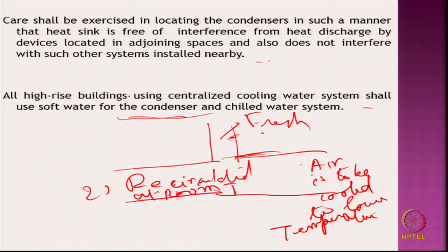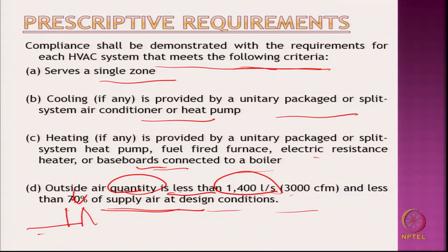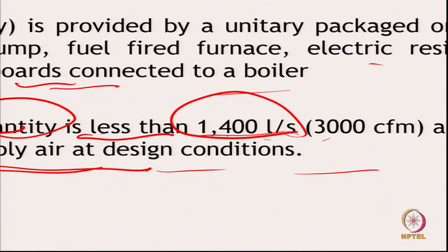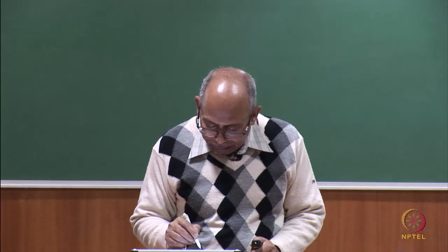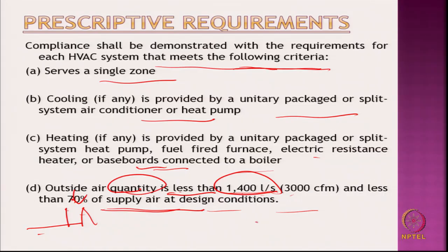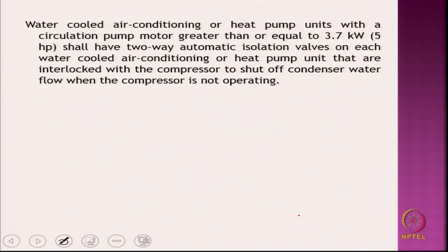Now, what it is saying is that I must have a fresh air requirement of less than 1400 liters per second or 70% of the supply air condition, 70% of the supply, that means 30% can be, right. So, outside air quantity shall be less, minimum 30% should be recirculated air, minimum 30. But usually it is much higher, right, so as to reduce the cooling energy requirement.